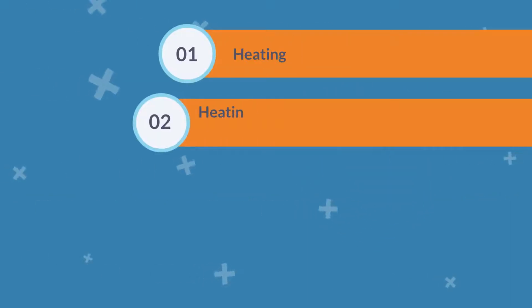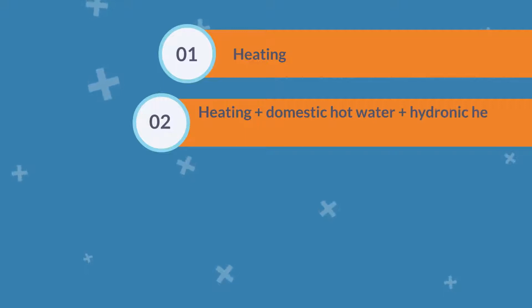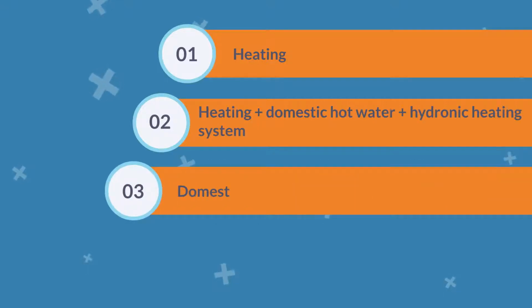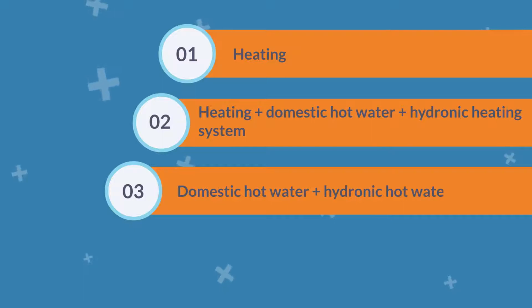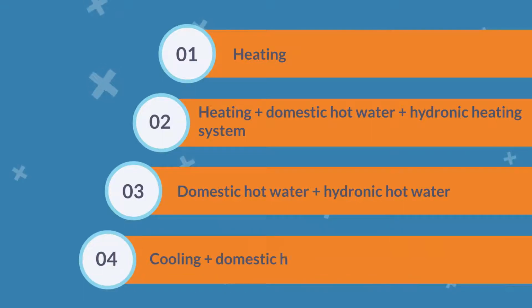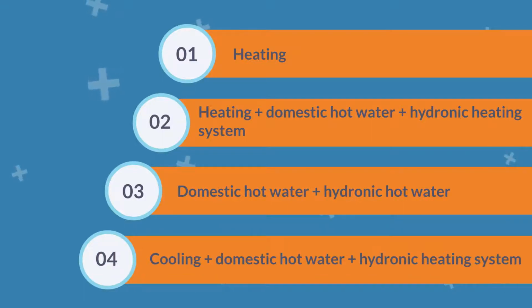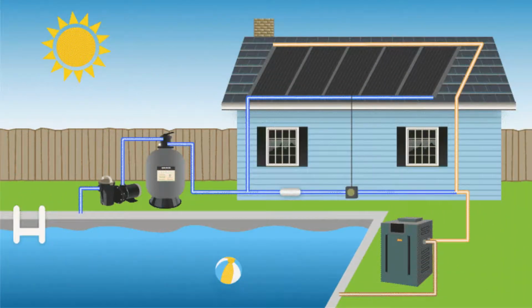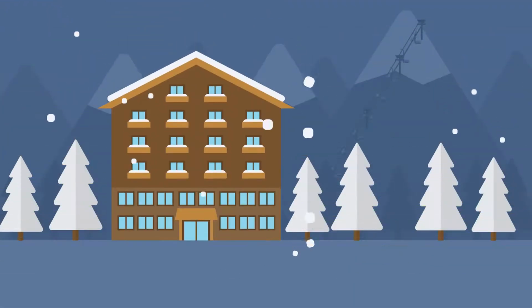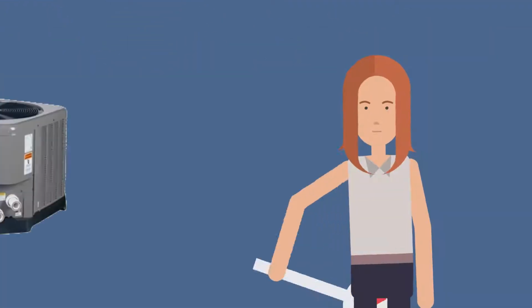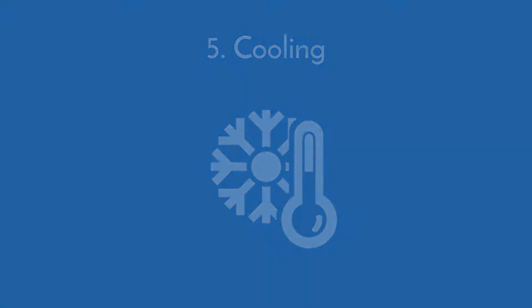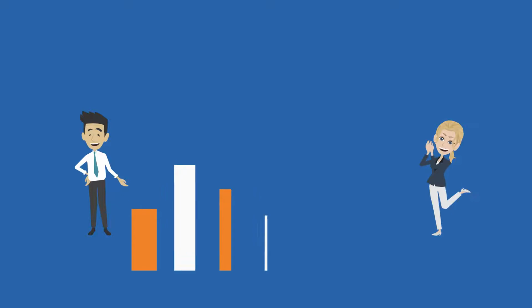A. There are 5 different situations in this appliance. 1. Heating. 2. Heating plus domestic hot water plus hydronic heating system. 3. Domestic hot water plus hydronic hot water. 4. Cooling plus domestic hot water plus hydronic heating system. In the summer, when you are taking a hot shower or warming up the pool water simultaneously, your house is cooling down. One side is for free, plus you don't need to have a pool heater as well. 5. Cooling.